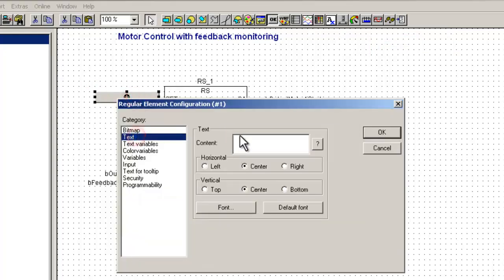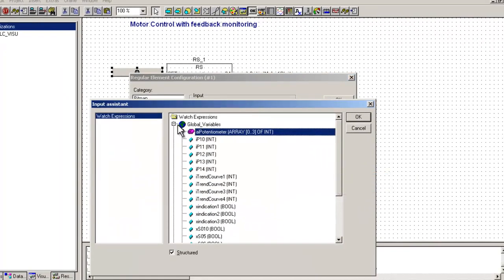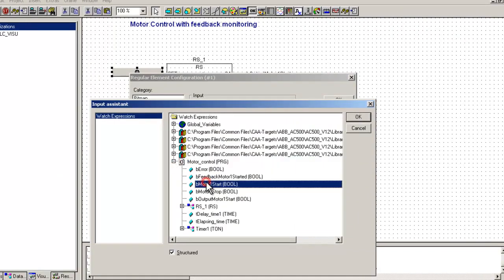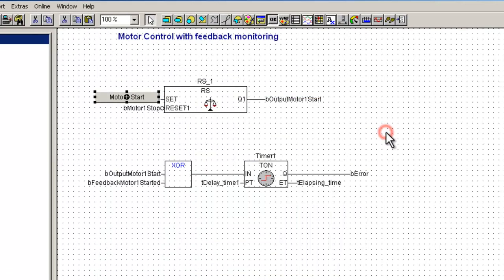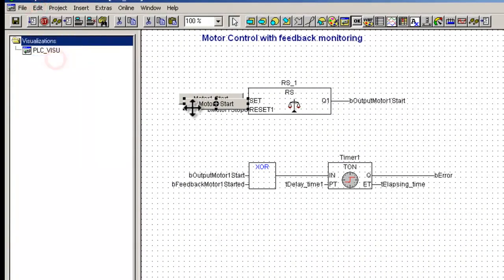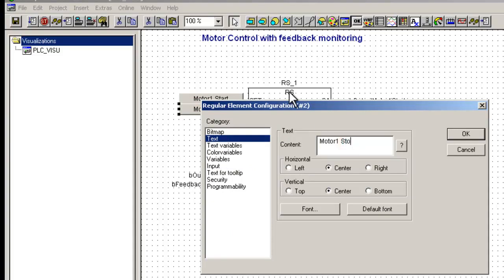Buttons could easily be configured with some actions like initiating or triggering some events from the visualization screen, in effect changing some tag or data values in the controller. In this example the buttons are configured like a push button, meaning pressing and depressing the button would send inverted boolean data to the controller. When we deal with objects that have the same property but different tags, we could make use of the simple copy-paste function, which ensures a uniform look and feel of the identical objects.